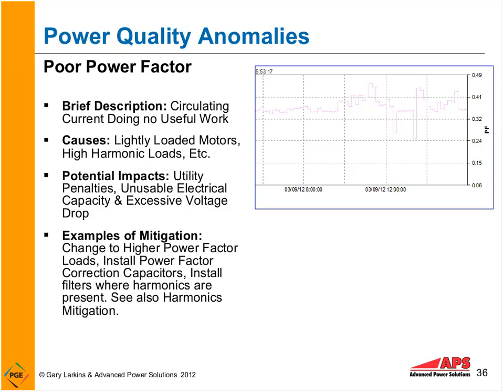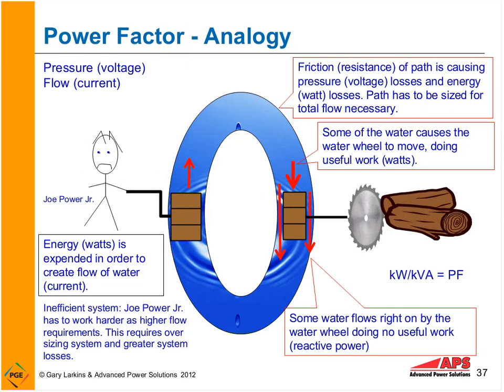So some mitigation: change to higher power factor loads, install power factor correction capacitors, but with filters where you have harmonics present. So what is power factor? Well, let's say over here on the left side, we see Joe Power Jr. here. Just to give you a quick example of what power factor is.